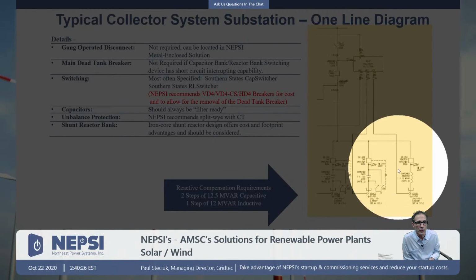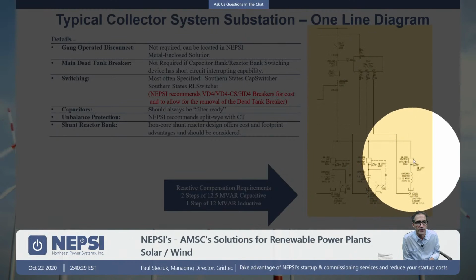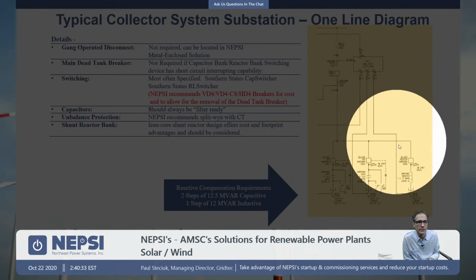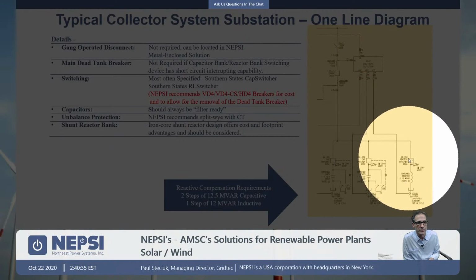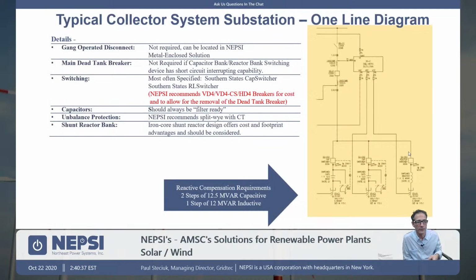And then over here to the right, you've got the shunt reactor bank. And again, if we make that a breaker, we're eliminating this breaker here. And the RL switcher, incidentally, has a higher cost than a comparable HD4 breaker that we would put inside our enclosure. So there are a lot of cost-saving opportunities here.